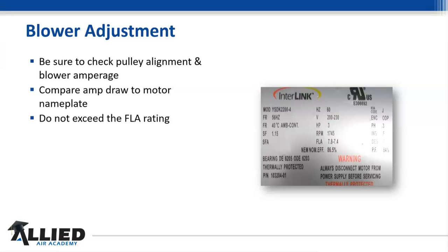When we set this blower up and we look at these tables and we get our airflow, you do not want to use up that service factor to start with. You don't want to be at 8.5, almost 9 amps whenever you first start this unit brand new. If you have to use the service factor from it brand new, go back and adjust it.